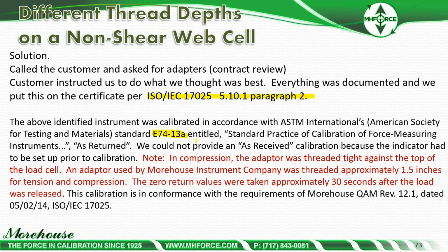Now we're in ASTM E74-18. But here's what we did. Note this in red. Note, in compression, the adapter was threaded tight against the top of the load cell. An adapter used by Morehouse Instrument Company was threaded approximately 1.5 inches for tension and compression. The zero return values were taken approximately 30 seconds after the load was released. The calibration is in conformance with QAM, blah, blah, blah.